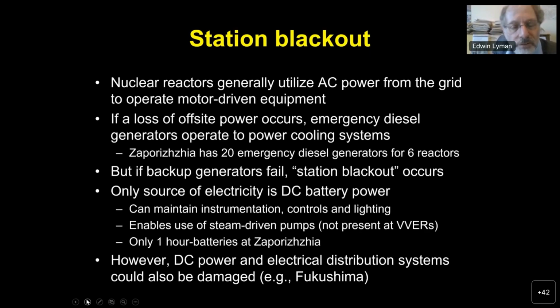But if all of the generators fail for whatever reason, then you can have a station blackout. And again, the units are not necessarily fully interconnected. So if you have a loss of power or a station blackout at one unit, it may, depending on the alignment of the electrical systems, be able to draw in power from an adjacent unit, but it may not be. So it could happen individually in any one of these units if the power system can't be realigned for whatever reason. And if all the generators fail, all you have is DC battery power, which is not sufficient to run the pumps. But it is needed to maintain instrumentation, controls and lighting.